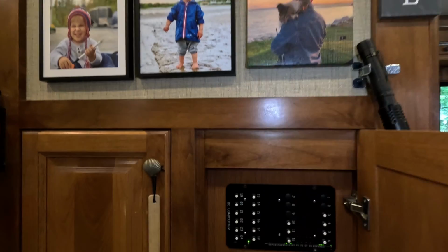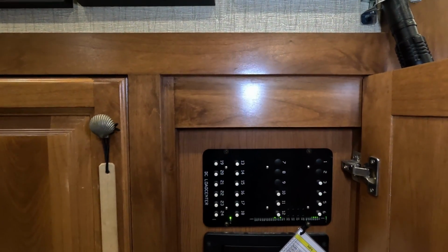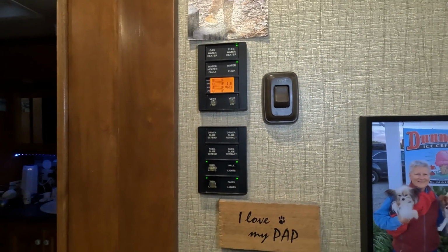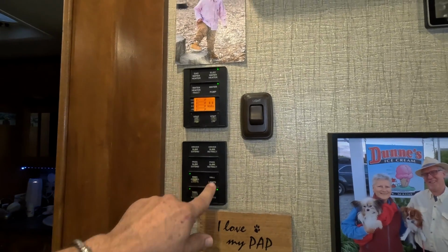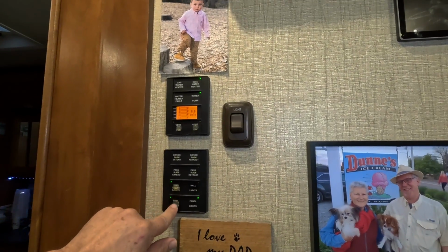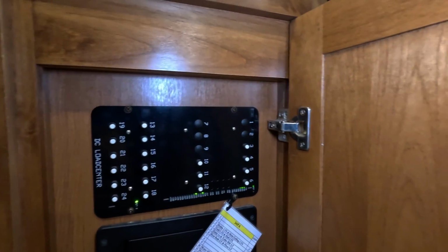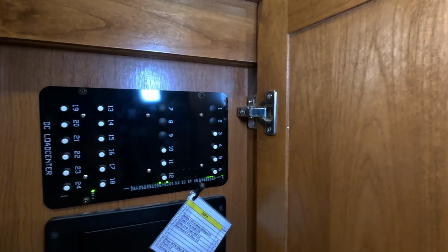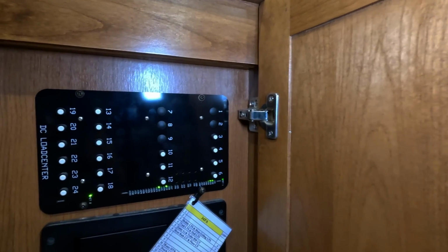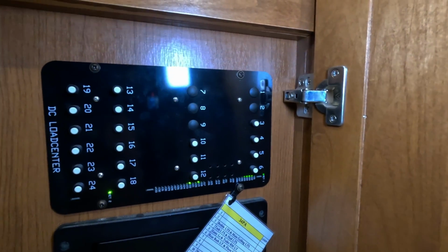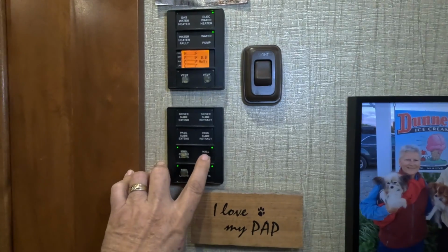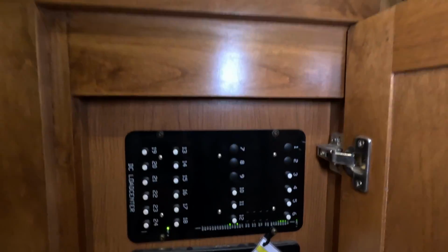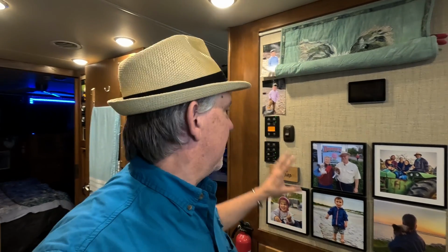So this is what's called the DC load center, and you've got your panels on the wall. So when I press one of these lights, if you look at the LED lights at the bottom, you'll see they come on. There, 103, 104 goes on, 104 goes off, 104 goes on. That's because you press this and the light goes on. So that's one of the first steps you can do in troubleshooting: is your signal getting from the wall panel to the central control system.